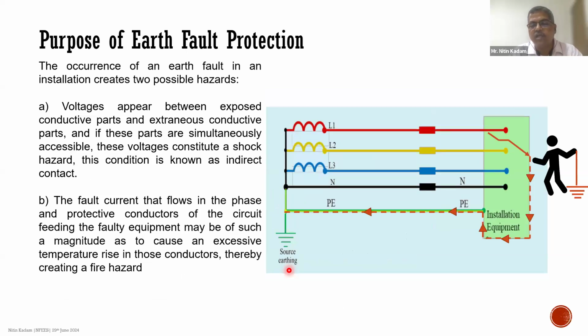Now, what is the purpose of earth fault protection? If you don't have it, in case of an earth fault, the conductive part of the installation or the equipment is going to become live. And the person who is touching the body of the equipment, if there is an earth fault going to the source earthing, and the MCB or the protective devices connected in the circuit are not tripping, then there could be a shock hazard. If the MCB is not tripping and the magnitude of the current is high enough, there could be excessive temperature rise, and that could also lead to fire. So earth fault protection helps us prevent shocks and also helps prevent fire in case of earth faults.